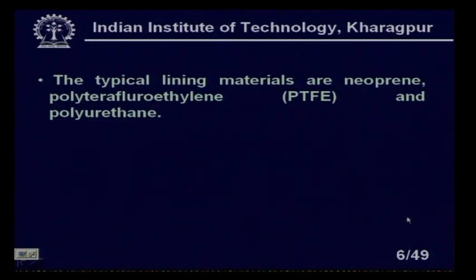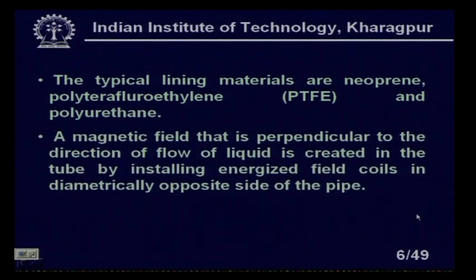The typical lining materials are neoprene, polytetrafluoroethylene (PTFE), and polyurethane. The magnetic field perpendicular to the direction of flow is created by installing energized field coils on diametrically opposite sides of the pipe. Two energized field coils are placed on diametrically opposite sides to produce the required magnetic field.